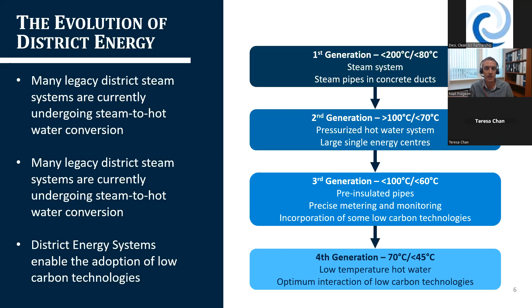District energy systems are operational throughout Ontario in municipalities, universities, airports, and government institutions. Currently, systems are split between using steam and hot water for district heating. Existing steam systems are now being converted to hot water based on efficiencies, and new district energy systems are trending to that lower hot water supply temperature, as shown on the previous slide.